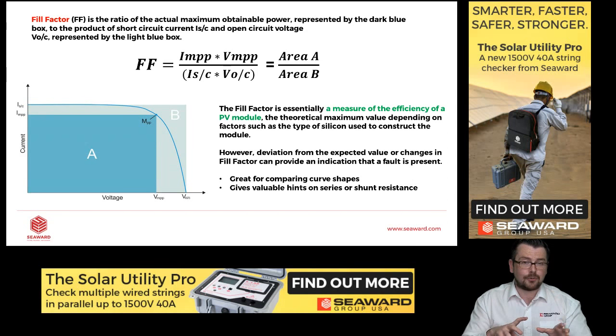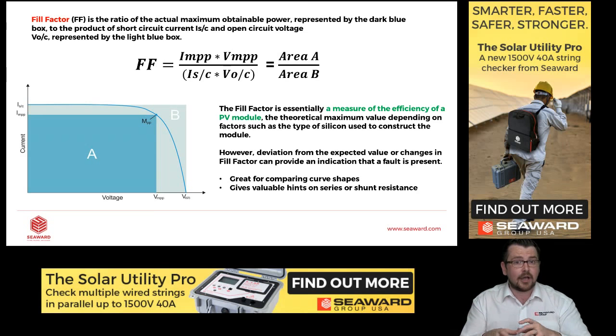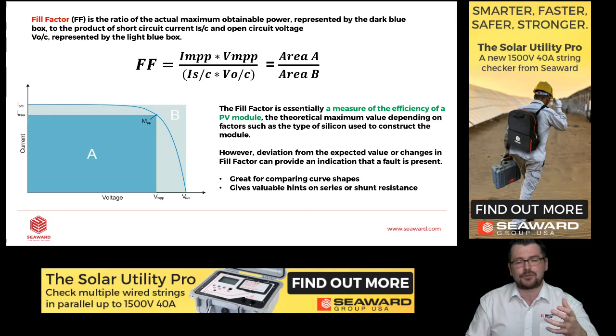So on our instruments, all of the curve tracers we provide, there is a fill factor indicator. So after you run the test, double check the fill factor, make sure it's not really low, especially if your measured VOC and ISC are not in line with your expected values.